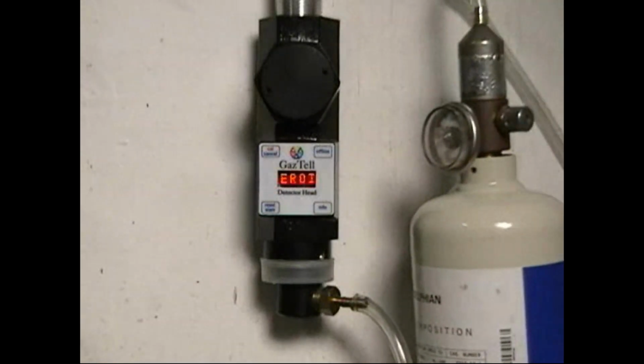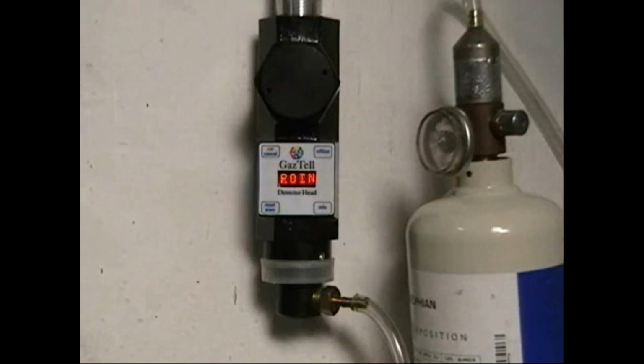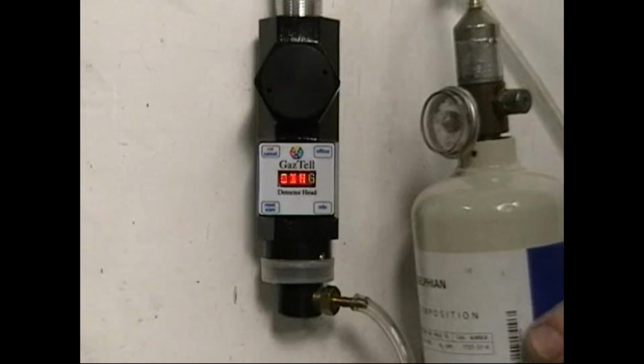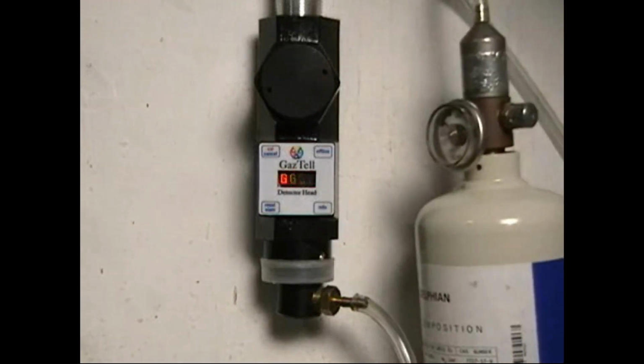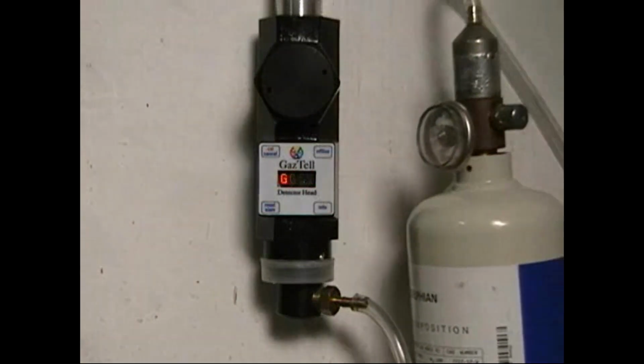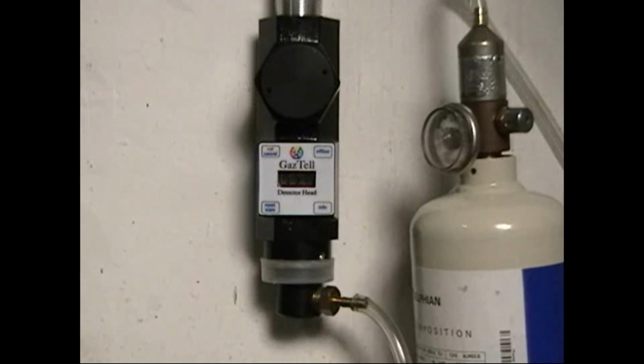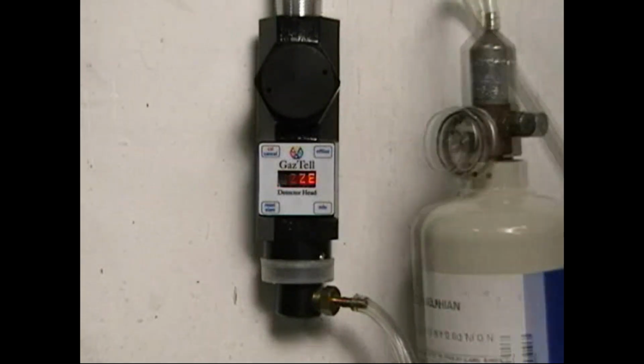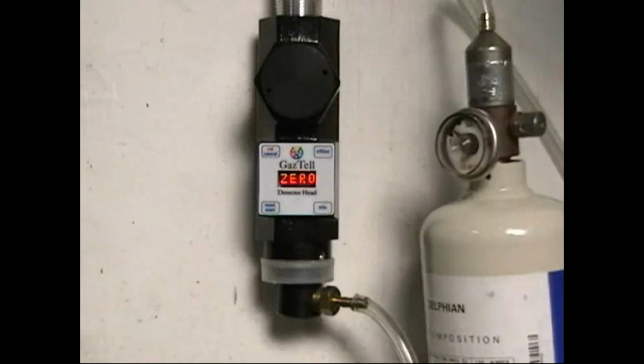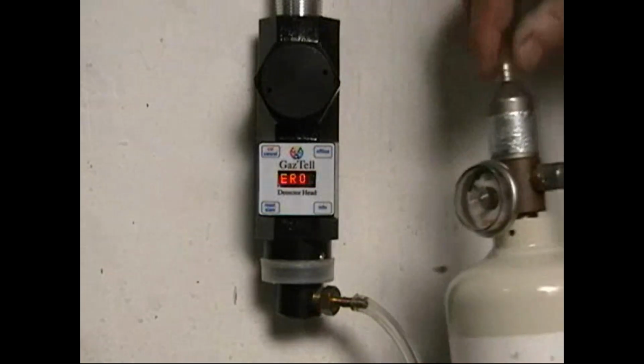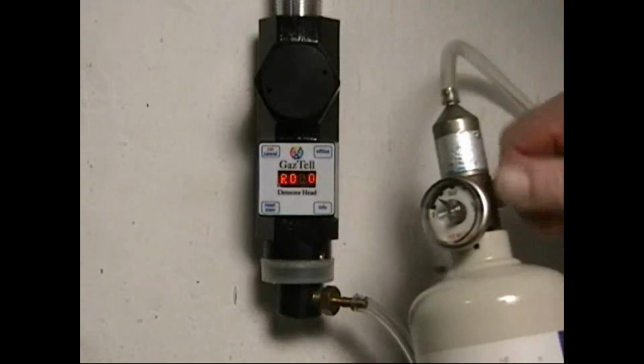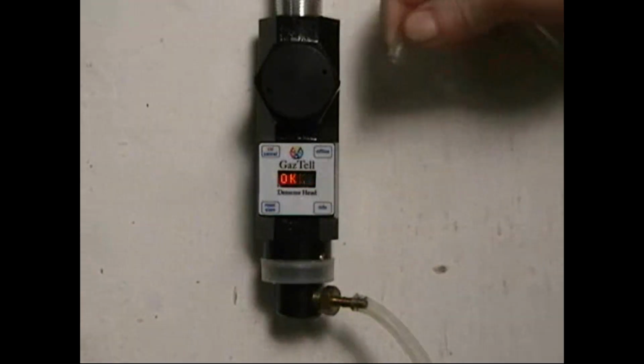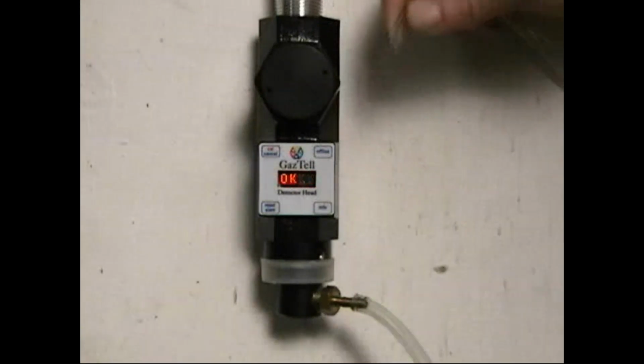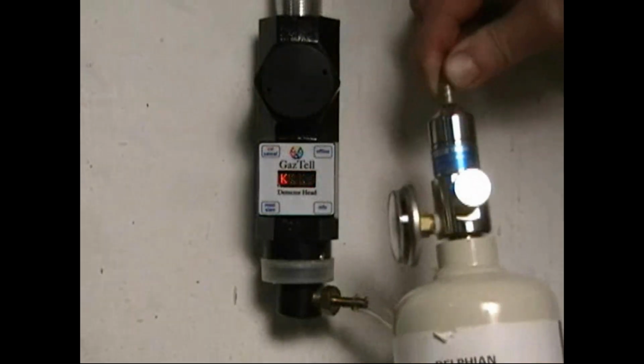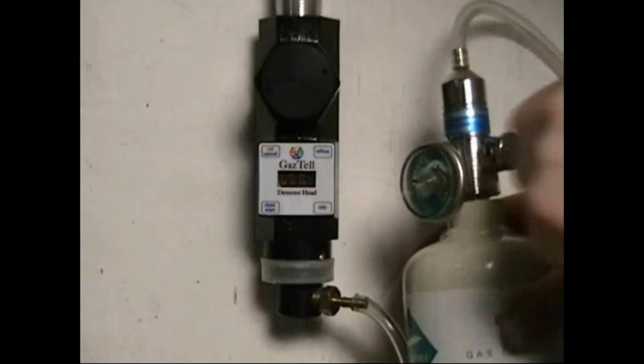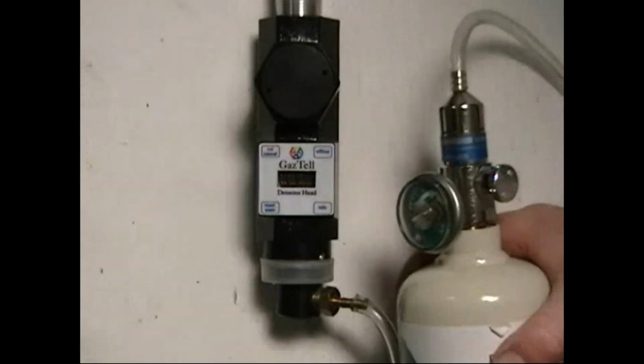If you get a calibration error, calibration has failed. An unsuccessful calibration may indicate an erratic sensor, a bad zero, or bad zero gas. You should make more than one attempt to calibrate zero. If the zero calibration was successful, nothing more is done. The detector will go back online after 120 seconds using the new zero calibration values. This is only true if the detector has been successfully calibrated before. If this is the initial calibration of a new detector head, span calibration must be performed. Make sure you turn off your gas valve.